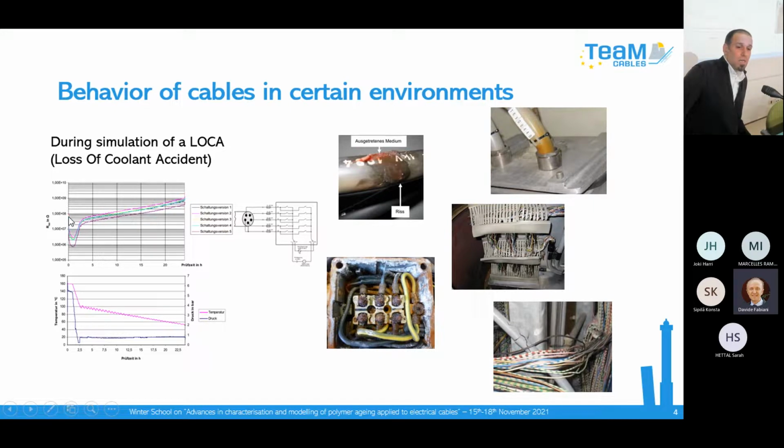What we see here is that when the temperature and the pressure increase, the insulation resistance falls. And we see here we are in the megaohm area, which can maybe be a problem for sensitive IR measurements.